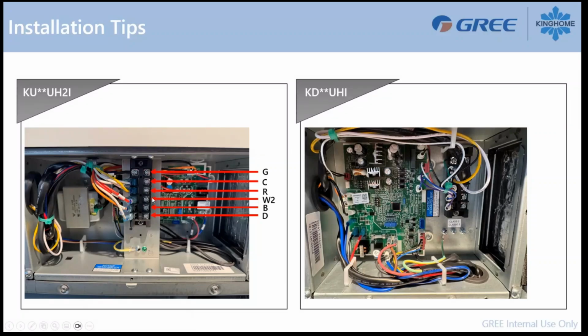You have the W2 connection here to start the duct heater. And just below you have your B signal here for the outdoor reversing valve. And the D connection at the very bottom here is the defrost signal. When the system outside goes into a defrost, you can send back a signal to the duct heater, to the air handler, sorry, and say you are in defrost mode right now.